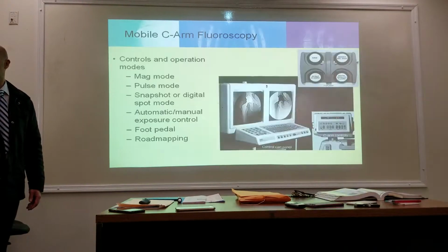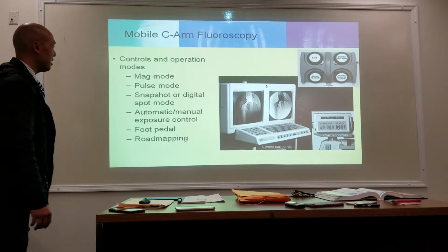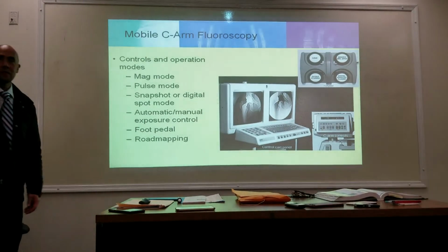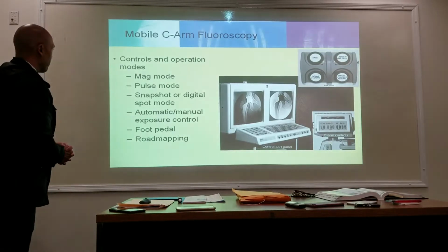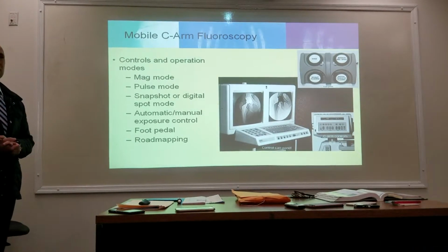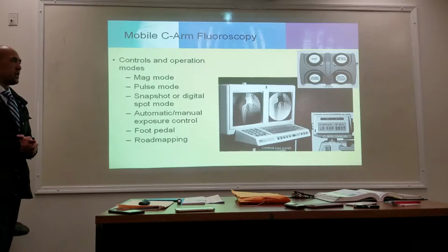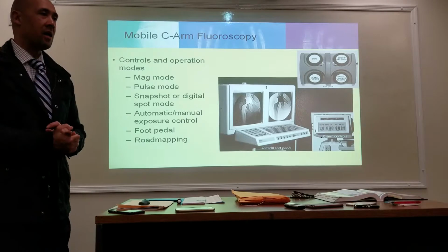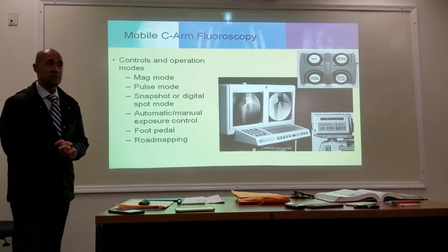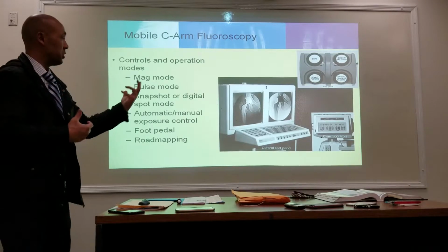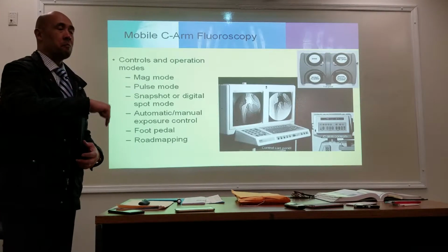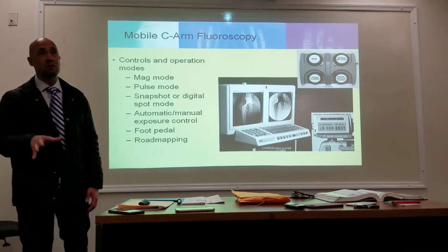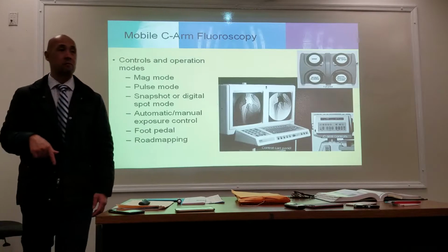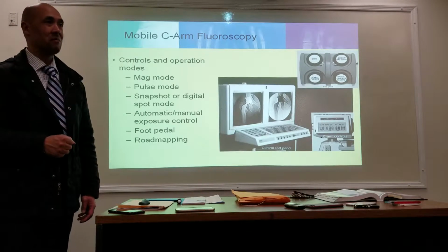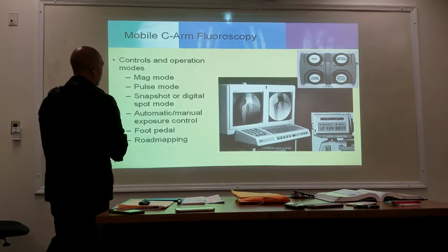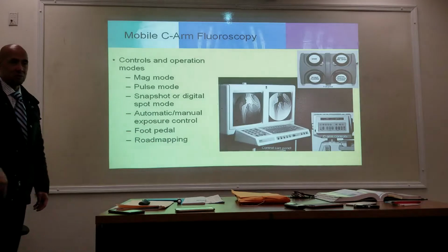Okay? All right. So these are the different features that the C-arm can provide. We have a mag mode. It just basically blows up the image. Pulse mode. I think we talked about that in radiobiology. Okay, this is where the energy is delivered in pulses. Is that bad or worse for the patient? Good. It's better for the patient because the energy is delivered in pulses. The images are visualized in pulses. So less X-rays, less exposure, but what is the downfall of using pulse mode? The image is not as good. Okay. So if the doctor wants a better image, you can always switch out of pulse mode.